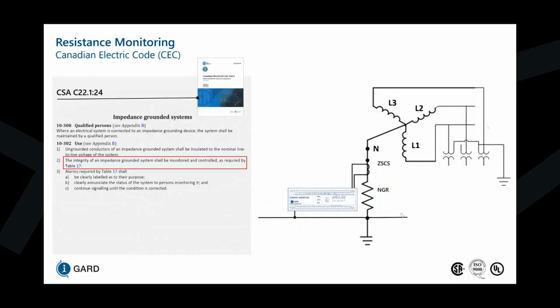So that's where, with our Sigma 3C monitor, we include a sensing resistor in parallel with the neutral grounding resistor. The sensing resistor gives us capability for getting a reference for the neutral voltage here and normalizing it between the R and G terminals back to the relay so that the relay can read what kind of voltage we're seeing at the neutral. We also have our CT connected for the current. And in addition to that, we're also using a high frequency AC injection, which is taking the path up through the neutral to the XO point and down through the NGR back to the relay.